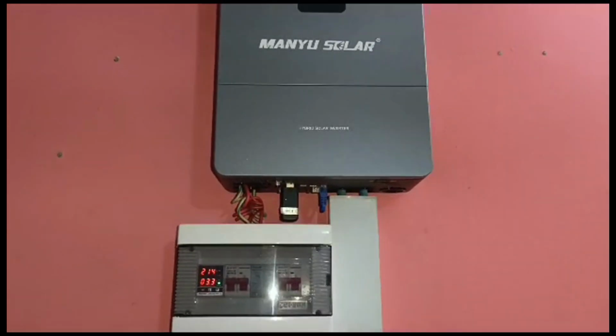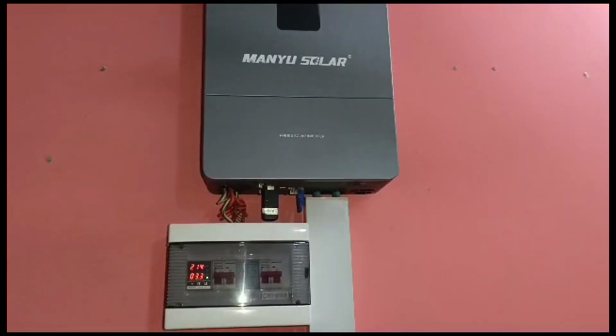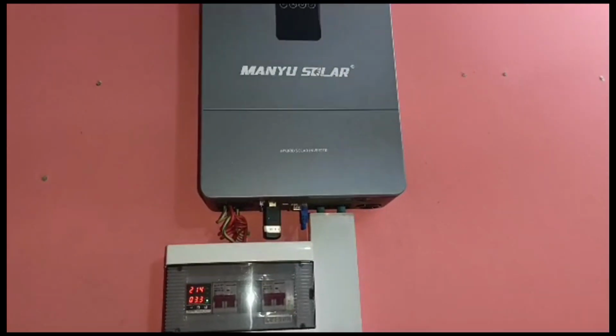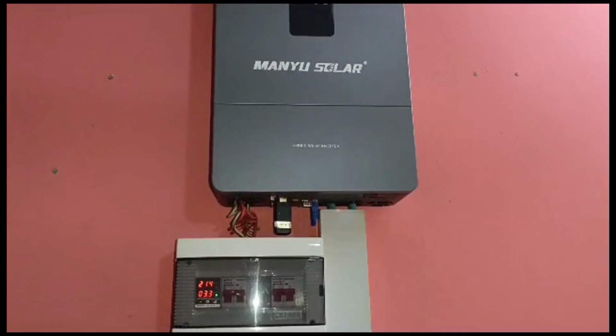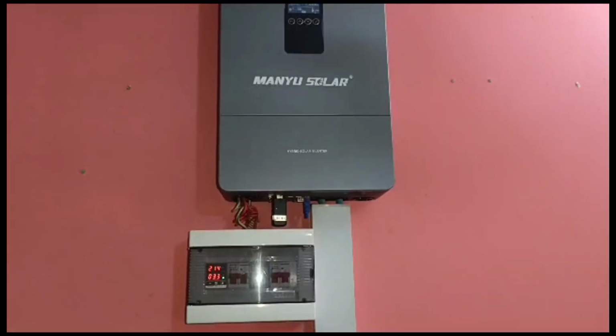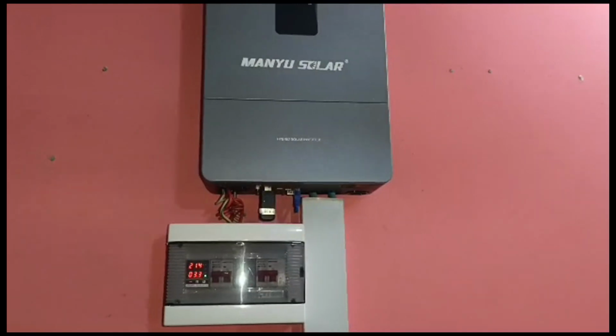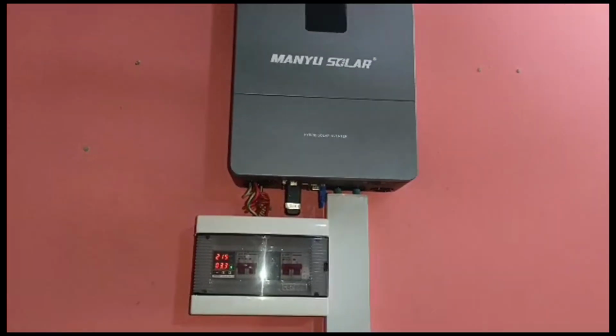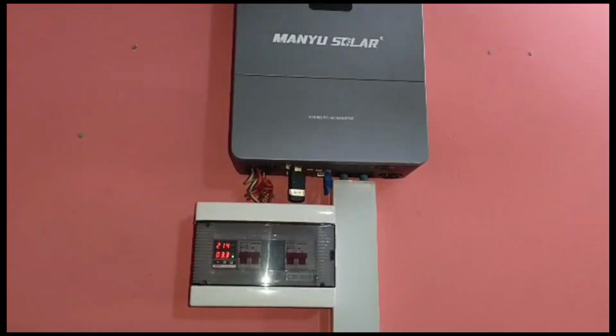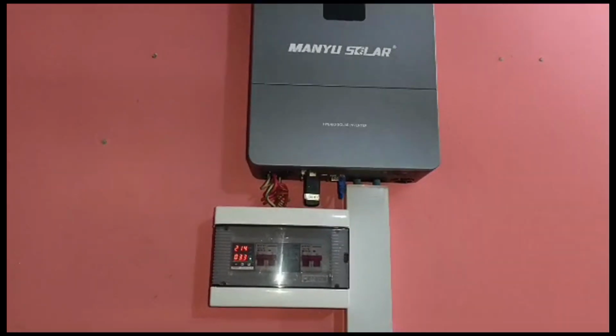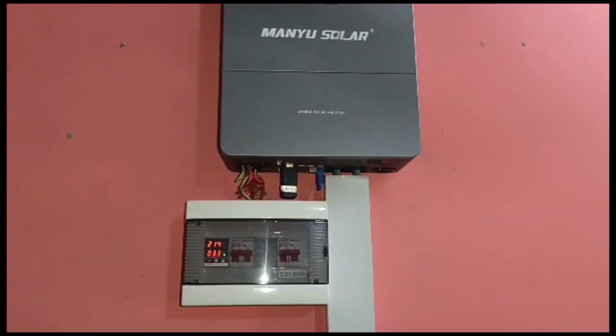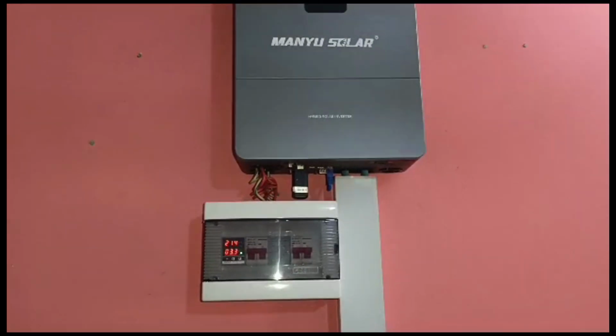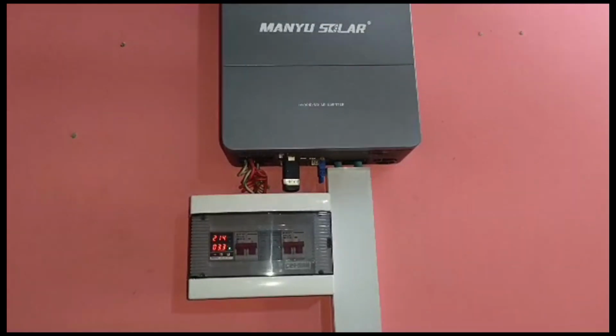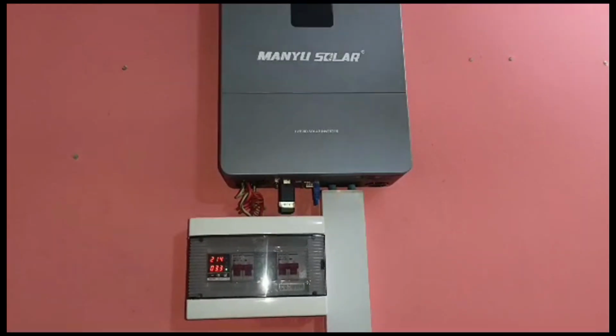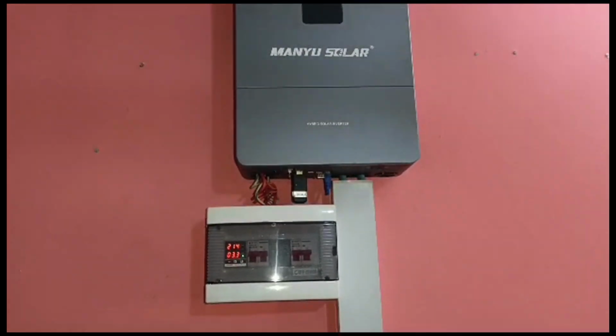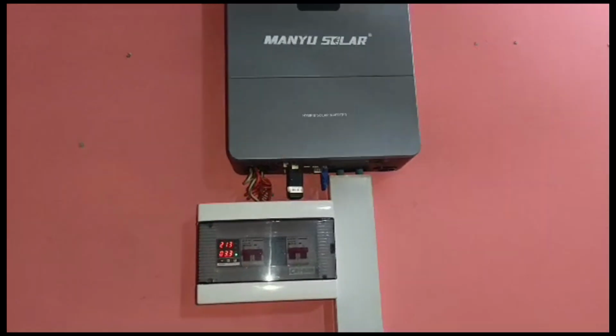So with effective use of the lightings and the fans, we can conveniently go 72 hours without having recourse to the grid. That's why the system is able to sit between the time of the grid outage and the grid coming back conveniently, because we depend on the grid solely for charging the battery. So streamlining the critical load to the most important is very, very important in this case.